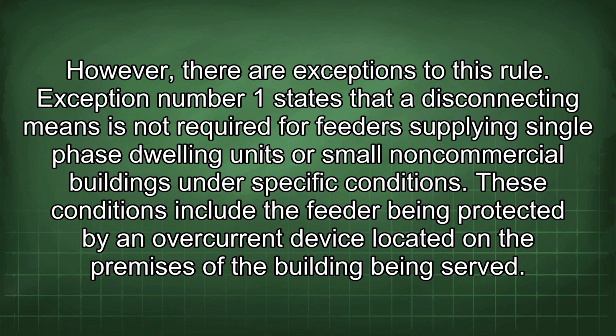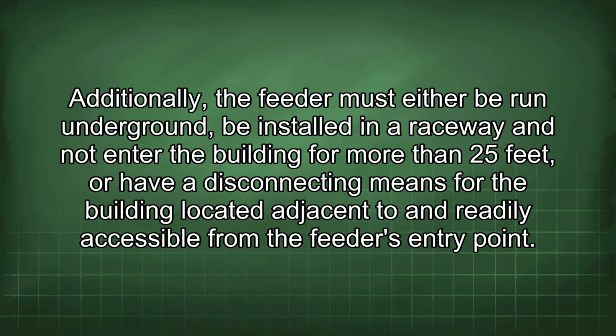Exception number 1 states that a disconnecting means is not required for feeders supplying single-phase dwelling units or small non-commercial buildings under specific conditions. These conditions include the feeder being protected by an overcurrent device located on the premises of the building being served. Additionally, the feeder must either be run underground, be installed in a raceway and not enter the building for more than 25 feet, or have a disconnecting means for the building located adjacent and readily accessible from the feeder's entry point.